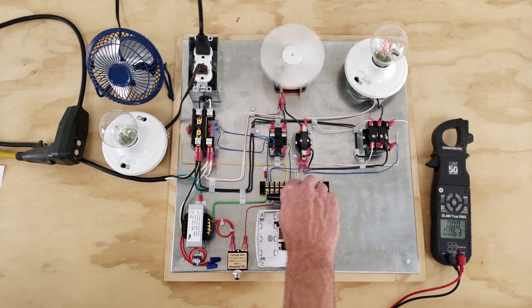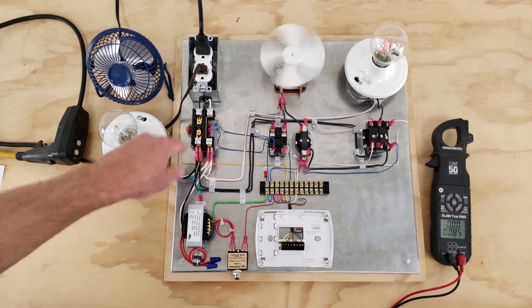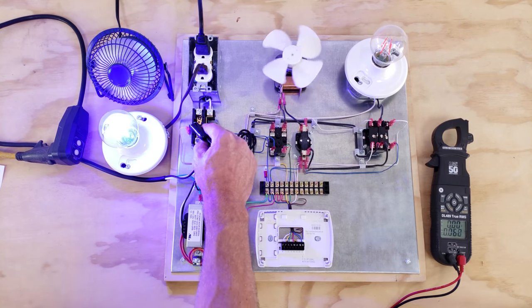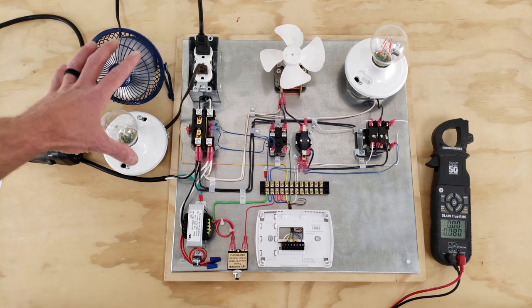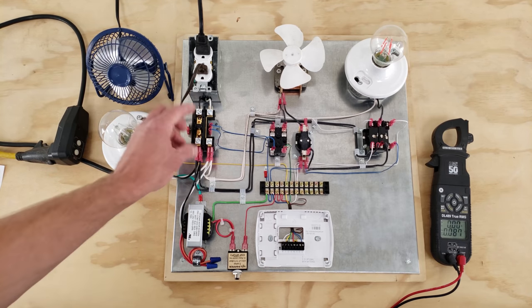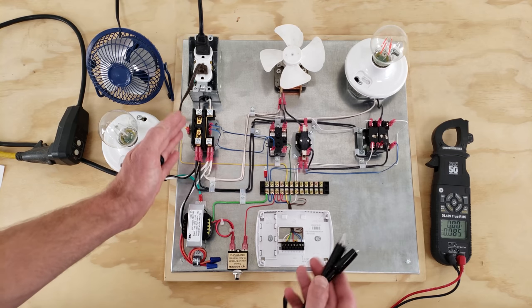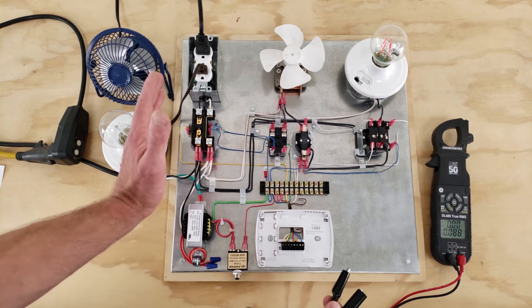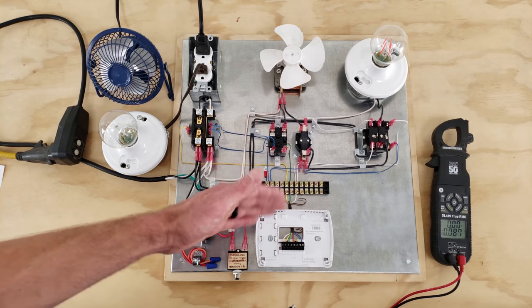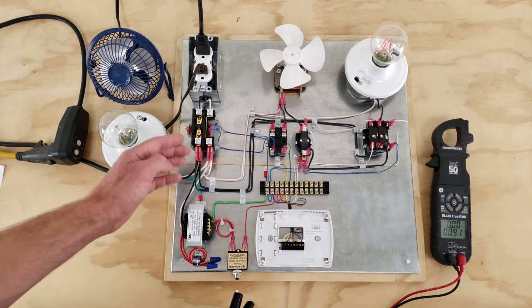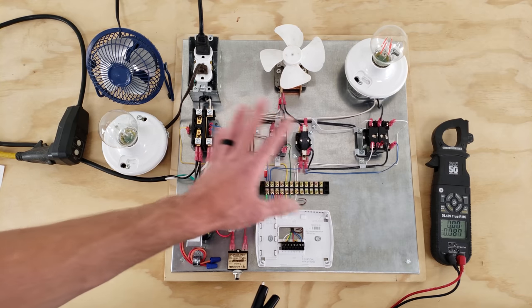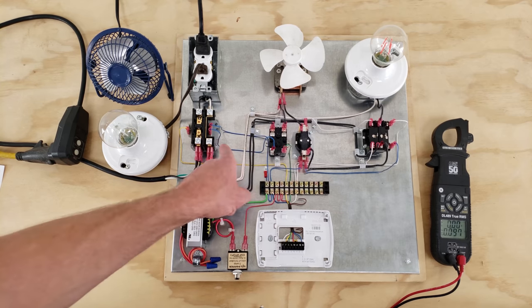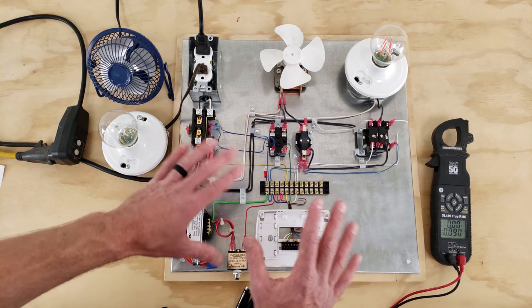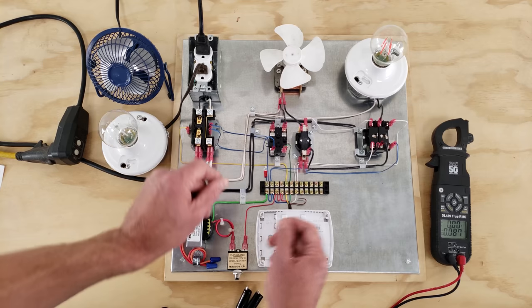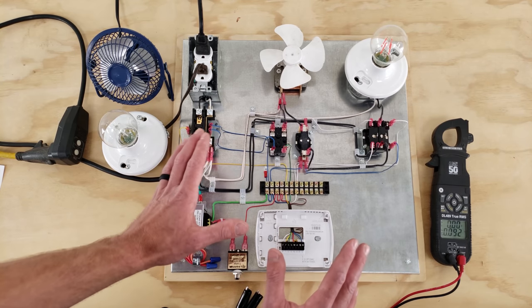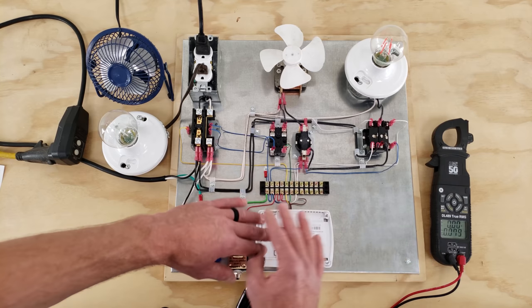Now, typically on a contactor, you're going to have a cover on this, and you can press this down in order to turn your outdoor air conditioning on, but basically your cover can cover over that. There's a lot of troubleshooting that can be done for each student. So if you have, say, 20 students or 10 students, you can set some faults in these ahead of time. It could be at your crimp connector or under your contacts in any of these components. You could have a shorted out coil, but basically what I did with my students is I made sure that they never started pulling wires off. They have to be able to measure it with their multimeter in order to prove that there's a problem.